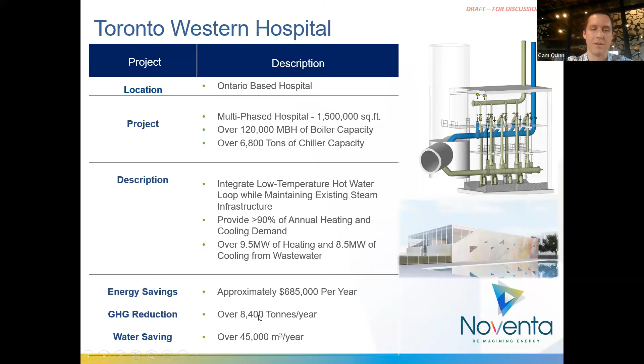One area I wanted to talk about was system integration. One of the unique things about this project is we're converting the hospital to low temperature hot water from a steam system. However, as we're only providing about 90% of their heating demand, we still need the ability for the steam system to supply heat. So, on this generic mechanical room schematic, we have hot water glycol coming to the mechanical room and going through the heating coil before it is returned back to our Noventa wastewater plant.